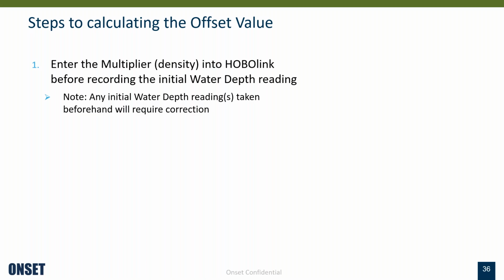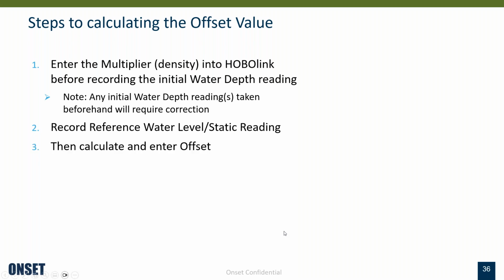I'll give a quick example of the steps to follow when calculating that offset value to account for reference water level. You don't have to remember all of this, but it's important to walk through it. If you plan to account for water density in your deployment, make sure you enter that multiplier value in HOBOlink before recording your initial water depth reading. If you don't do it initially and later enter a water density value different from 1, you'll have to correct those initial values, since the multiplier changes the reading. Then you record your initial reference water level, or static reading, and calculate the offset.